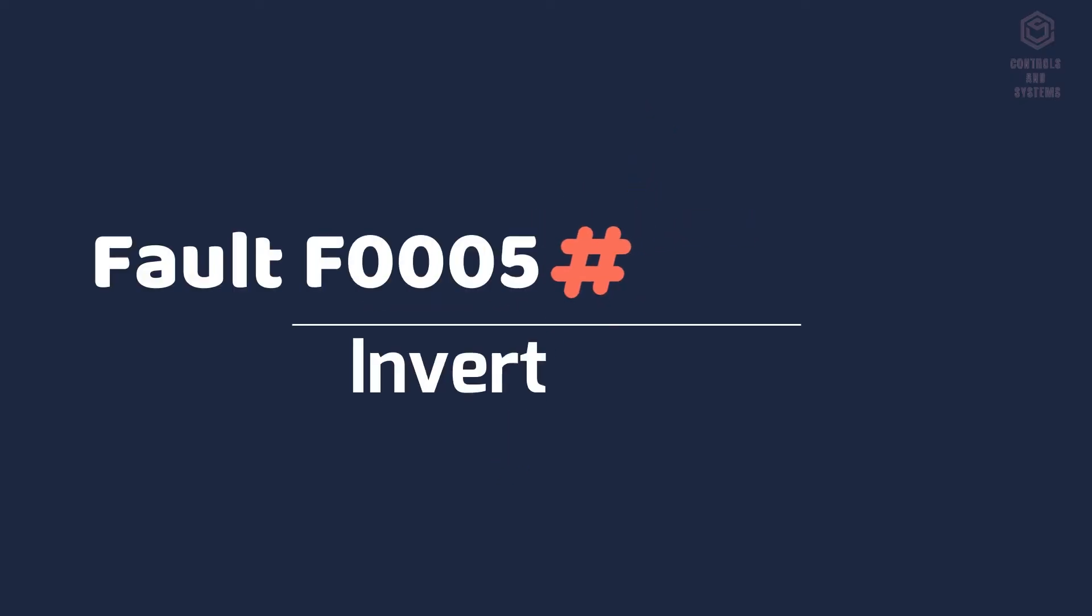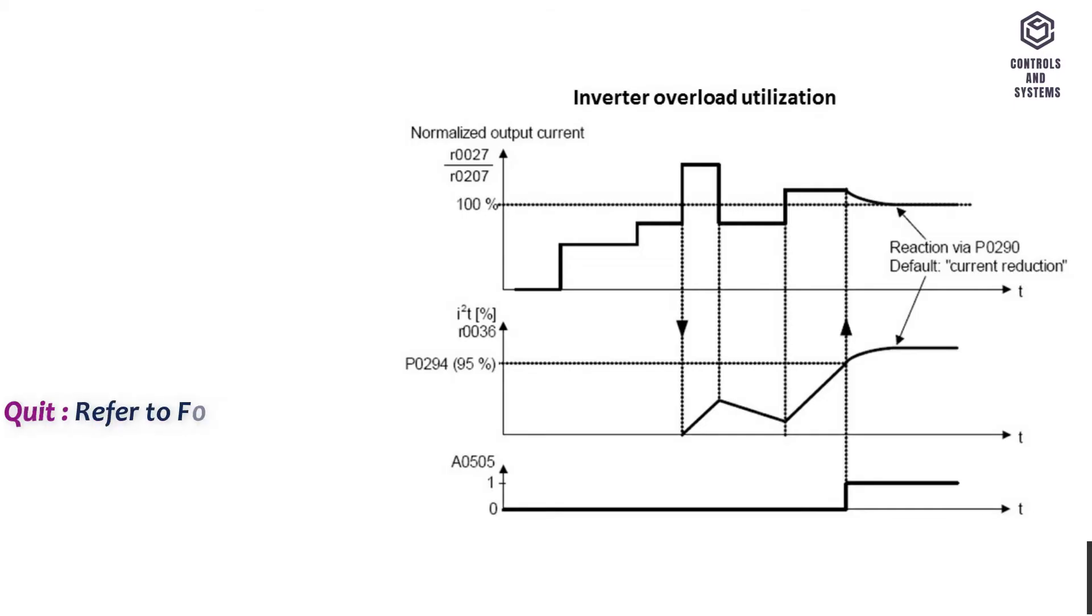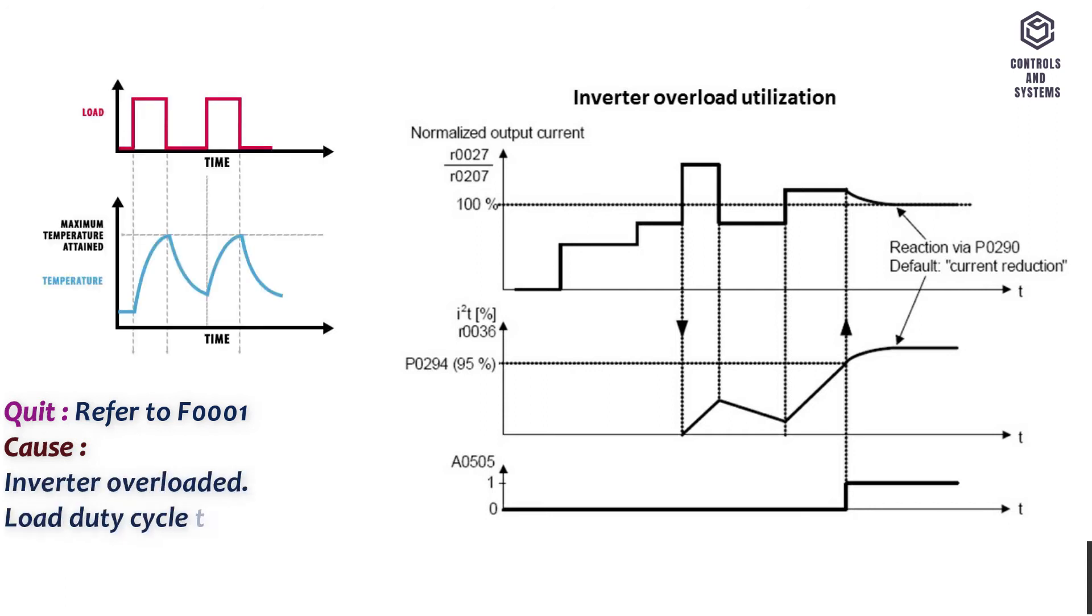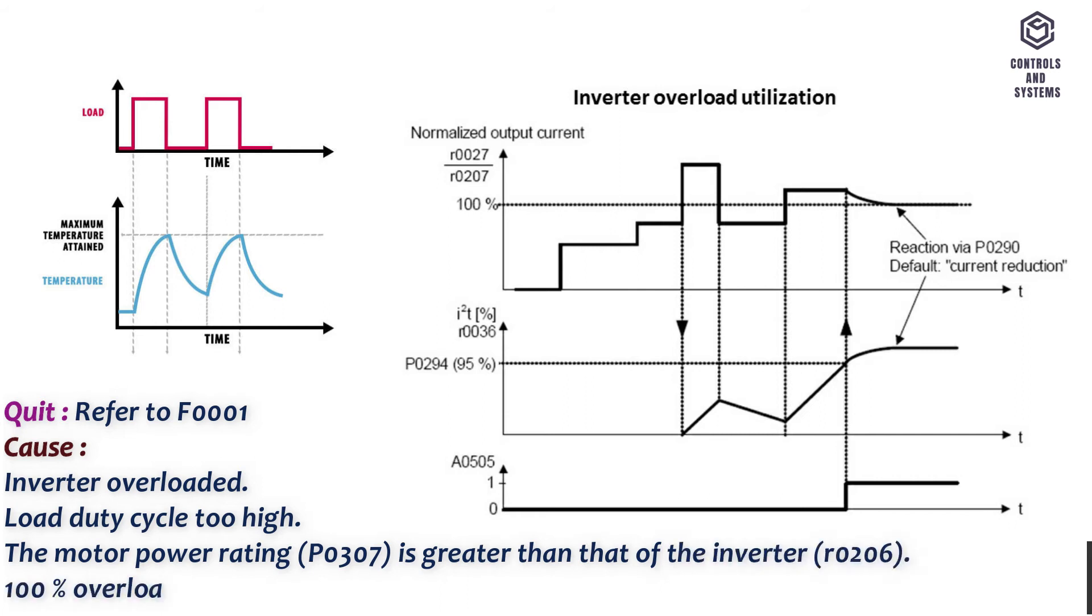Fault F0005 inverter I2T. Quit: Refer to F0001. Cause: Inverter overloaded. Load duty cycle too high. The motor power rating P0307 is greater than that of the inverter R0206. 100% overload reached, refer to utilization R0036.